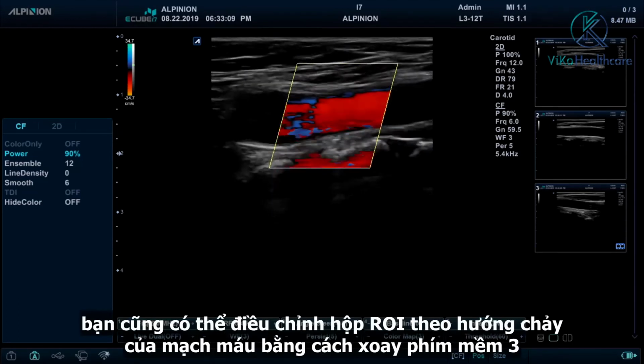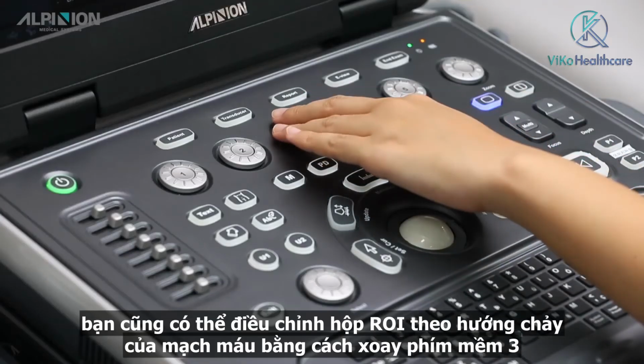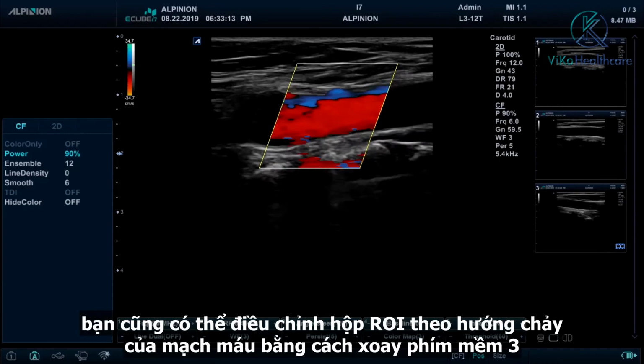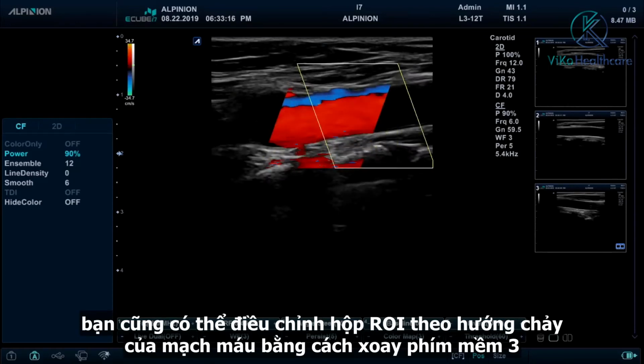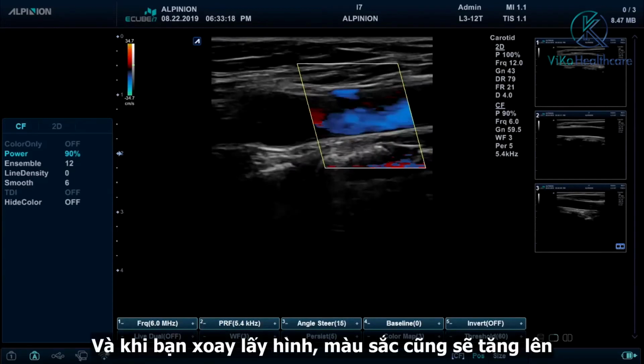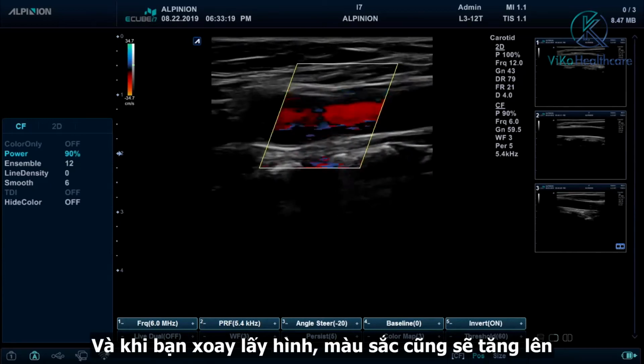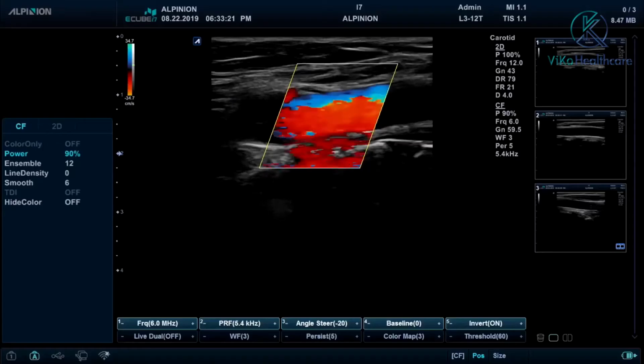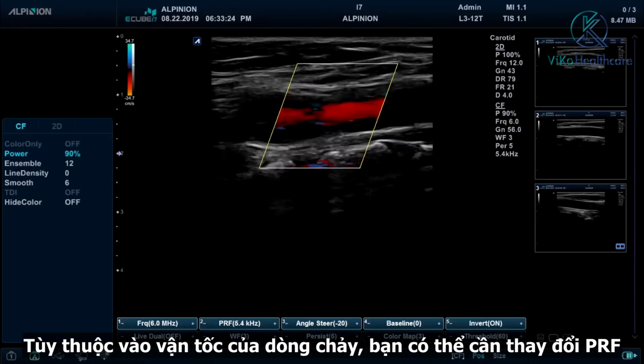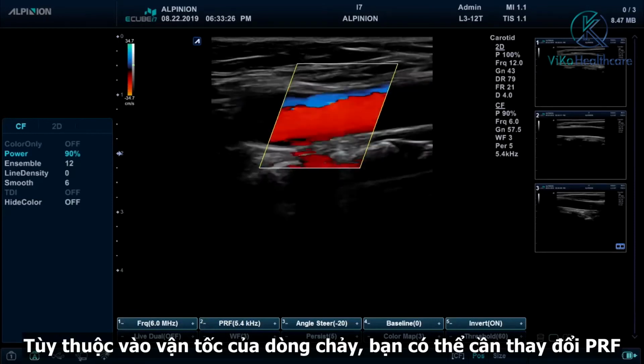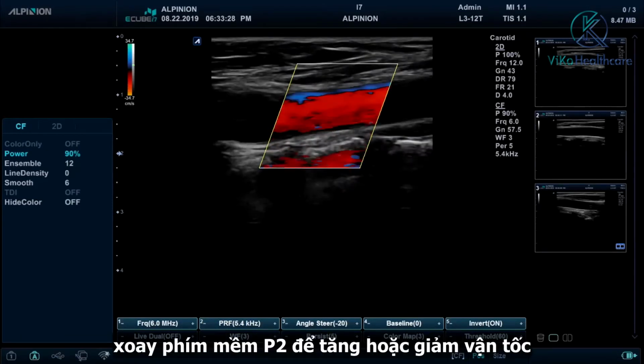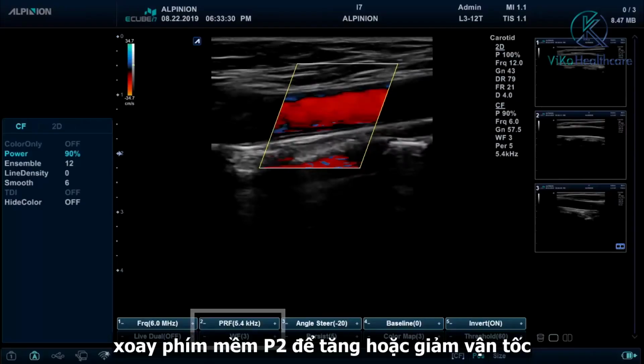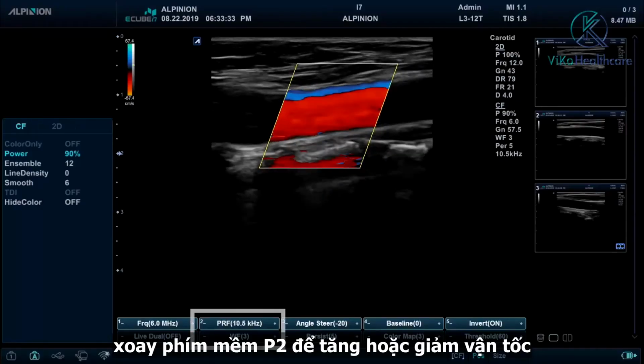You can also steer the ROI box according to the flow direction of the vessel by rotating soft key 3. And as you rotate the gain, color gain is increased. Depending on the velocity of flow, you may need to change the PRF. Rotate soft key 2 to increase or decrease velocity.